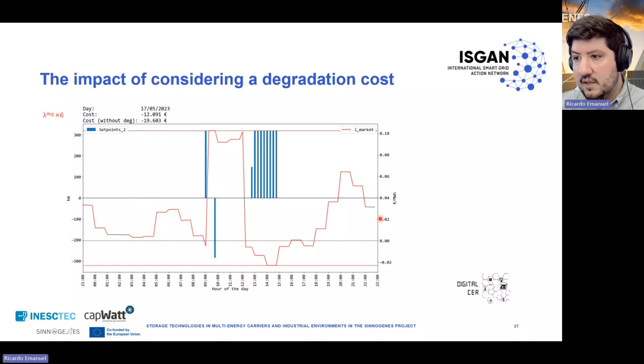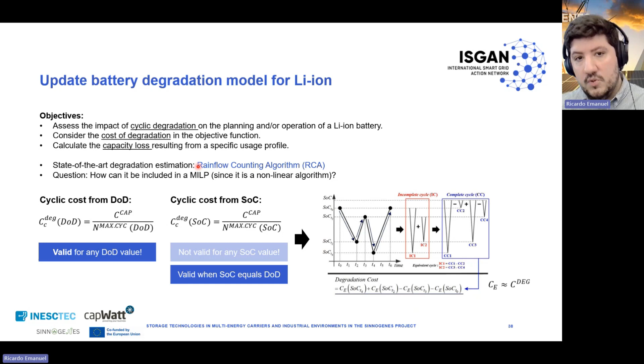So we found another algorithm, the rainflow counting algorithm. This is the state-of-the-art degradation estimation model for batteries, and it counts the number of cycles the battery has performed. Usually the manufacturer tells you how many cycles you can perform until end of life, so based on that we wanted to estimate how many cycles we were performing on our daily schedule. That's highly nonlinear, so we found a way to introduce the rainflow counting algorithm into our MILP problem. We are now testing the difference between calculating cycles post-delivery versus within our model.